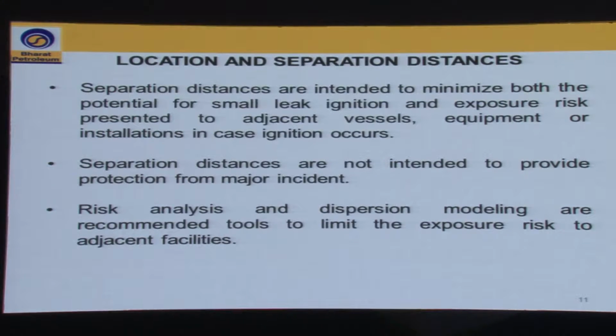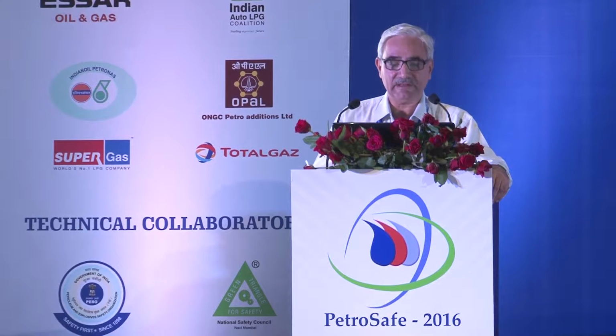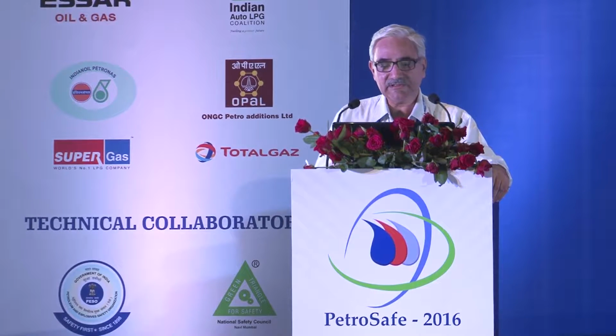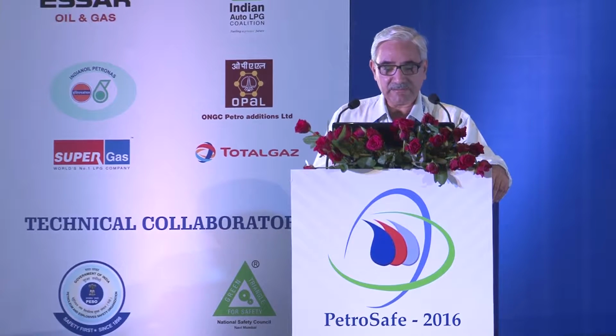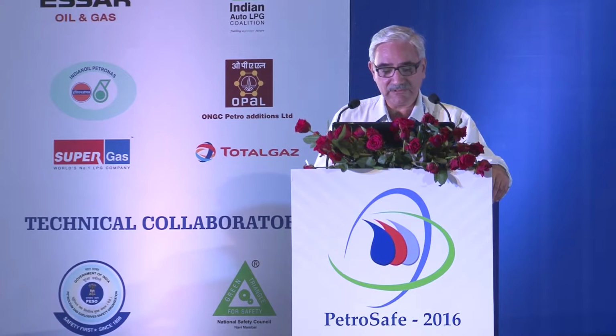But in a mounded bullet also, though it is covered in the mound, there are certain inter-distances which we are supposed to maintain. Separation distances are intended to minimize both the potential for a small leak, ignition and exposure risk presented to adjacent vessels, equipment or installations in case ignition occurs. Separation distances are not intended to provide protection from a major incident. Risk analysis and dispersion modeling are recommended tools to limit the exposure risk to the adjacent facilities.